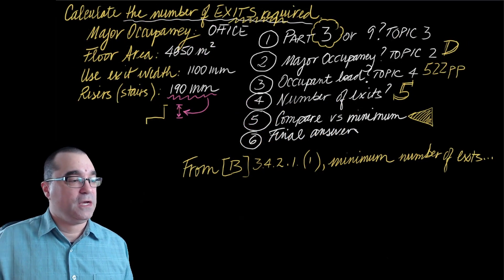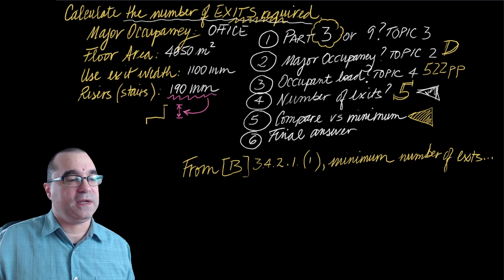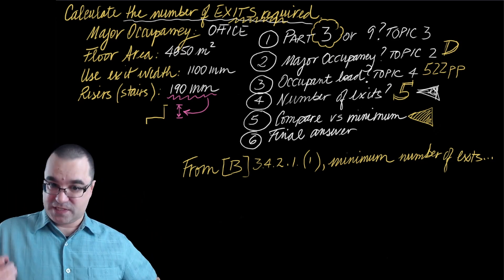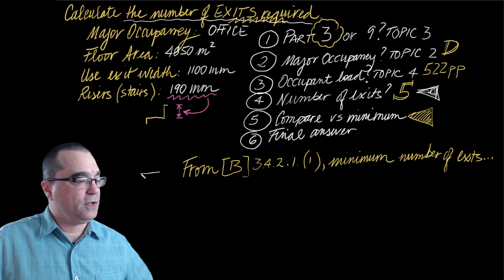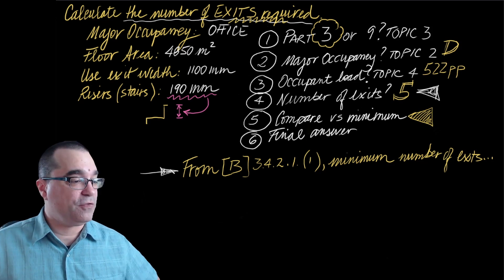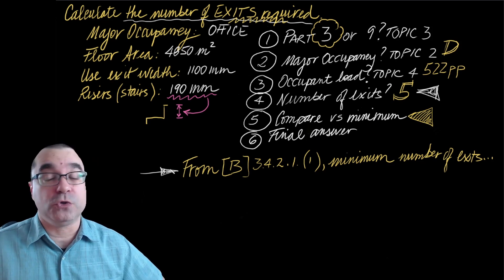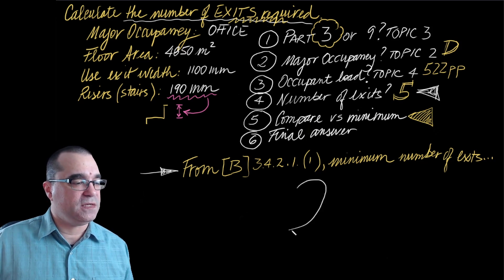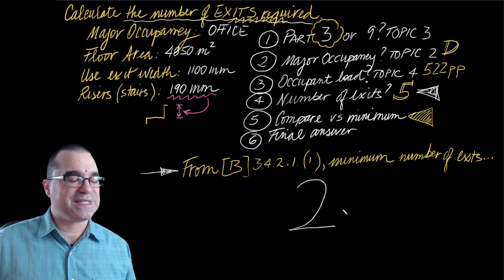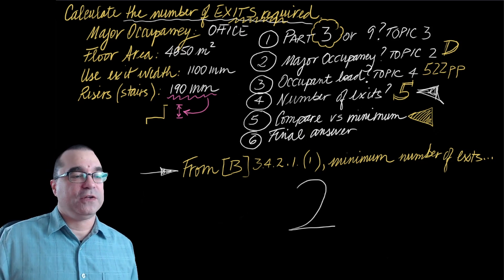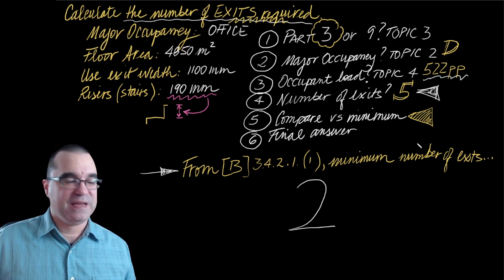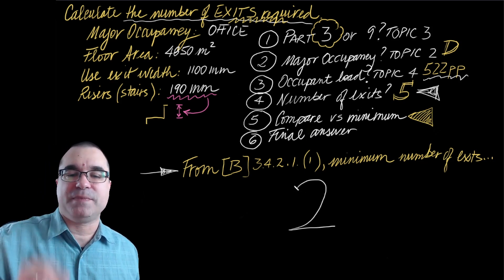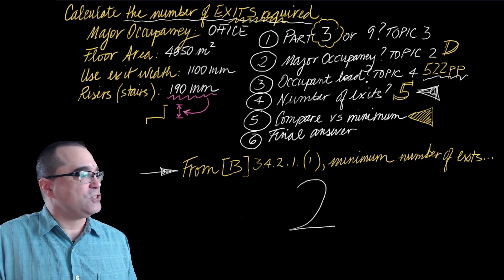For step number five, we have to use the number of exits that we calculated right here. And we have to compare it against the smallest number that the building code says you must have for this kind of situation. So the appropriate location in the building code where to find the minimum required number of exits is under sentence 3.4.2.1(1), which says that the minimum number of exits you must have is two. So what does that tell us? We find that the 522 people require five exits. We find that the building code says you have to have at least two exits.